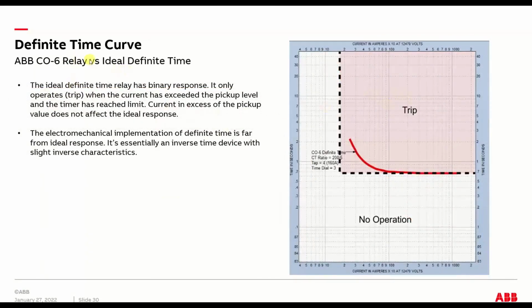Here's an explanation of the last important one, which is definite time. Definite time means that if the relay picks up, it times to a certain preset number and then it trips. The historical stuff, and some stuff that's still around today, is not exactly that; it's more this red curve than it would be the on-off. So just be wary of that.